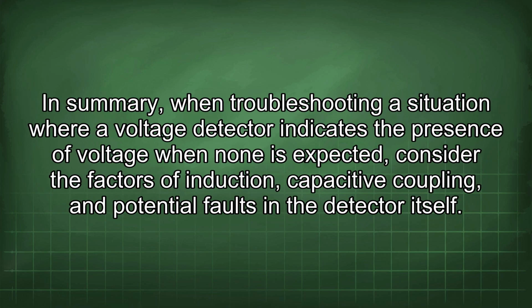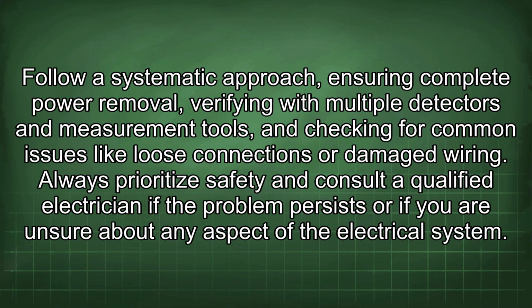In summary, when troubleshooting a situation where a voltage detector indicates the presence of voltage when none is expected, consider the factors of induction, capacitive coupling, and potential faults in the detector itself. Follow a systematic approach, ensuring complete power removal, verifying with multiple detectors and measurement tools, and checking for common issues like loose connections or damaged wiring. Always prioritize safety and consult a qualified electrician if the problem persists or if you are unsure about any aspect of the electrical system.